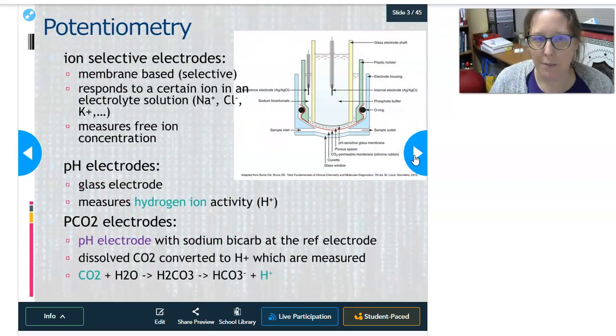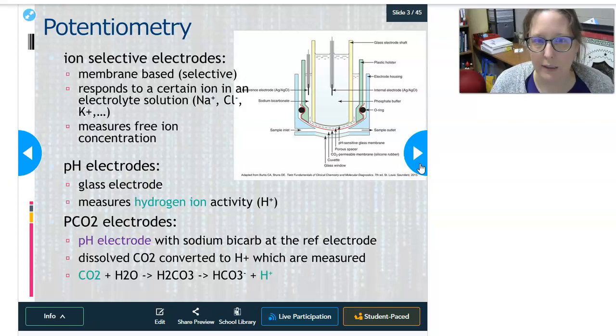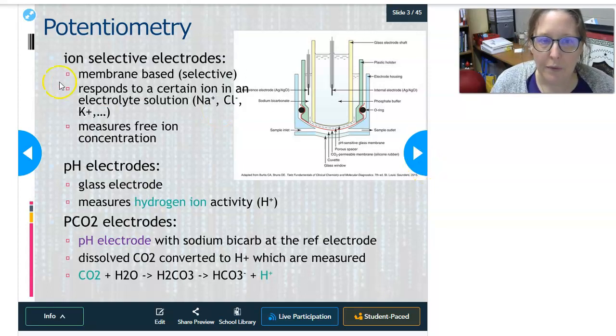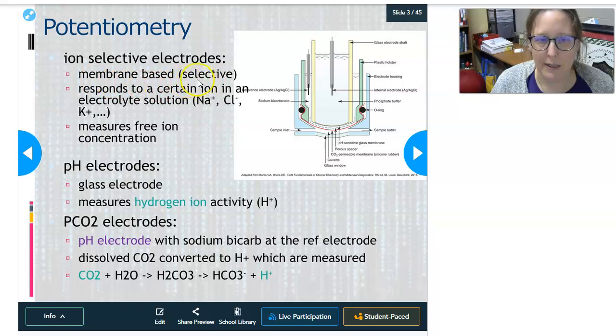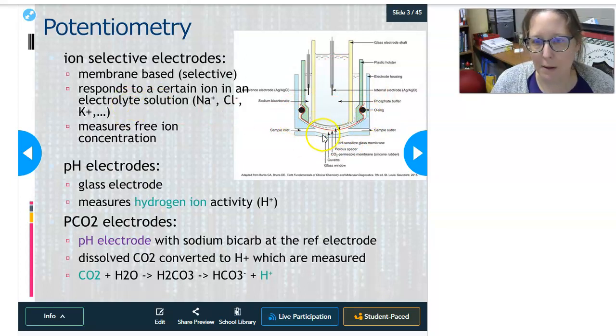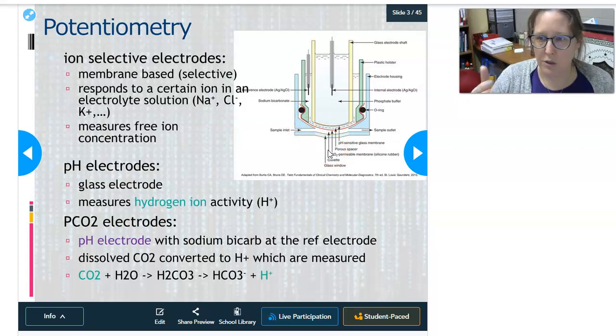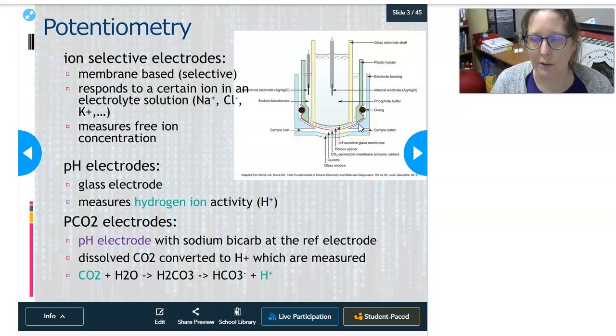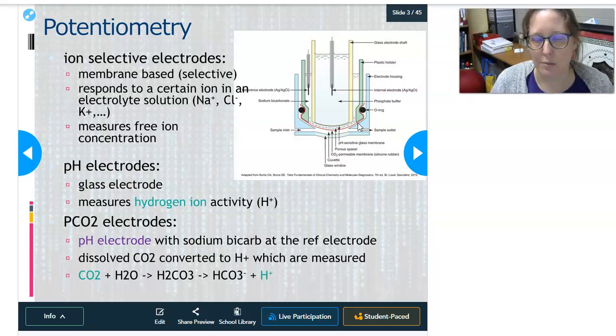An example widely used in large chemistry analyzers is ion-selective electrodes. The ion-selective electrodes, or ISEs, are membrane-based, and that is the selective part. This is a general schematic of an ion-selective electrode, and there's a membrane that will allow a certain ion to cross over to the exclusion of other ions. There's usually a specific electrode for each ion that you're trying to measure.